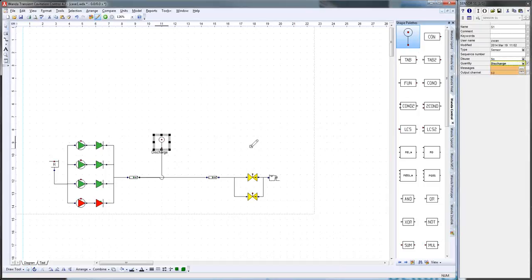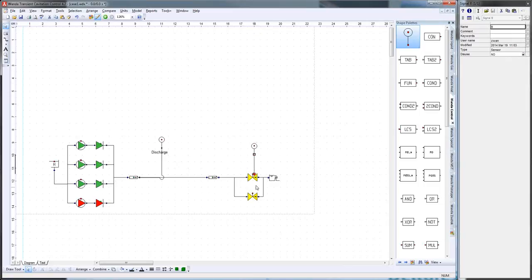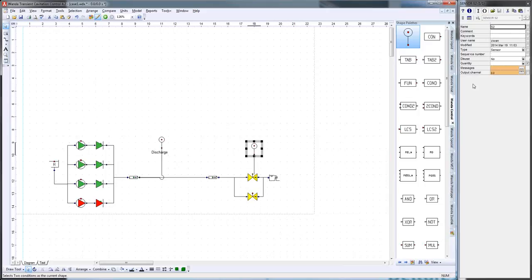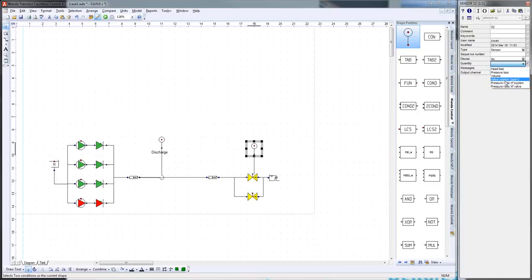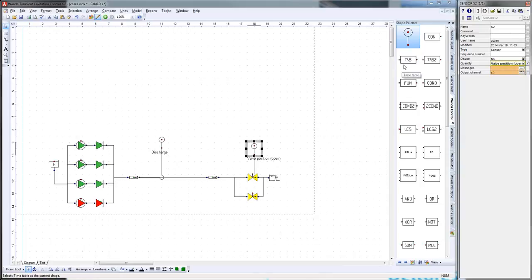What you also can do is use a sensor connected to the control point of a component. For example, I can connect it to the control point of a component, and then if I look at the list, it's a different list. I can measure the component-specific outputs, like for example for a valve, you have the valve position, but also you can measure the pressure loss. Now let's put it to valve position. And finally, you can connect it to the nodes - I can connect it here to this node. If I then look at the drop-down list, I can measure the quantities of the node, so for example, I can measure the head.